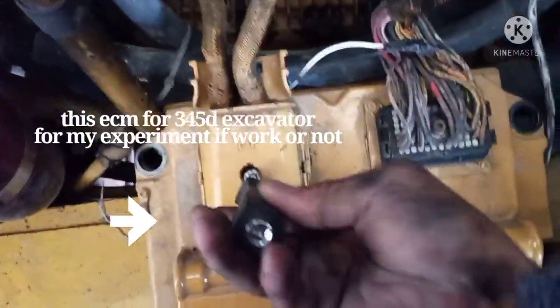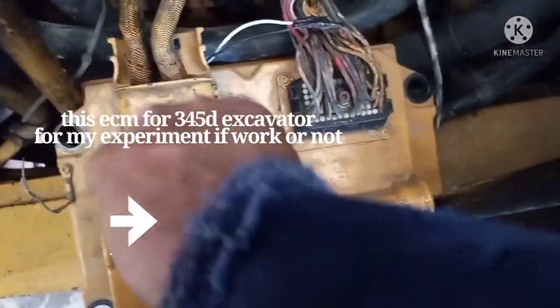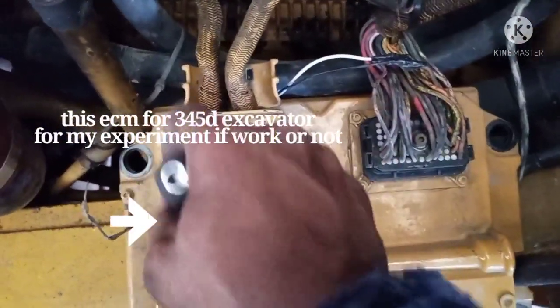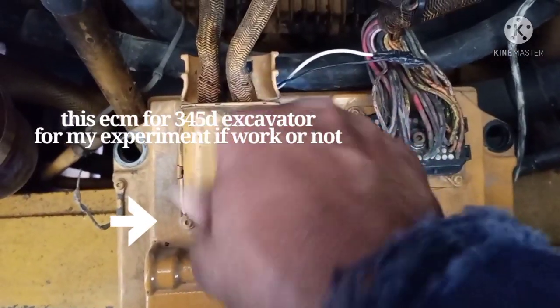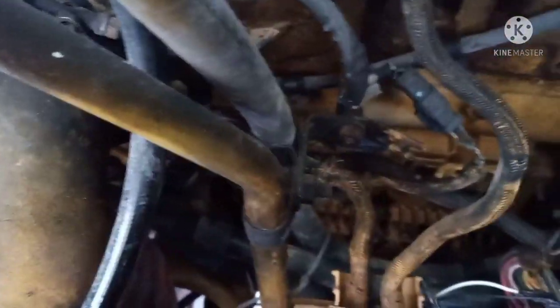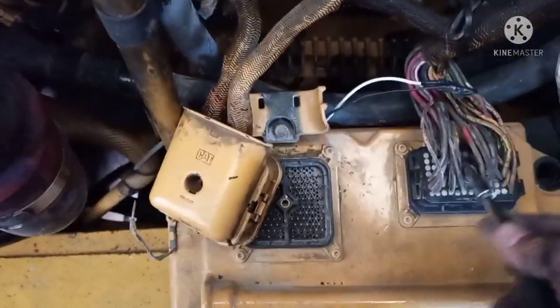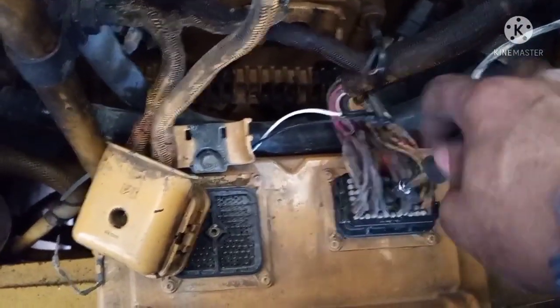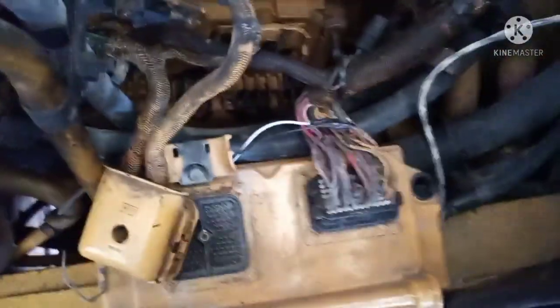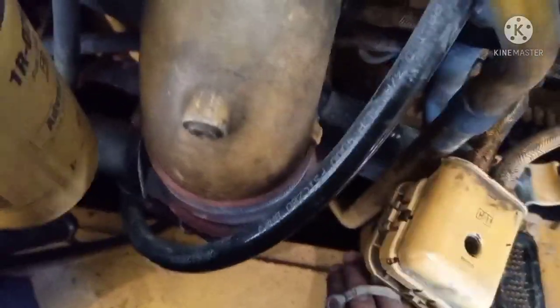Again, this is the removal time of this ECM. I would like to tell everyone, this ECM is for the 345 machine, used for testing in a 966. Okay, as you can see, I already removed it. And then I'm going to fit the other ECM that came from the other 966 shovel. This troubleshooting is not easy because the ECM is not just a small amount of work. But luckily I have another shovel breakdown here. It is an engine problem, so it's easier for me to troubleshoot.